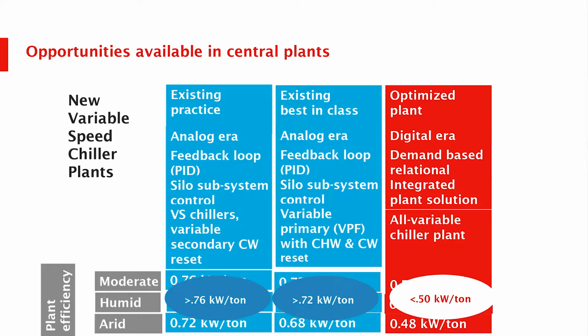I don't want people leaving the room saying the guy from Armstrong said if I do this I'll end up with a plant at 0.5. But we have definitely seen plants that are considerably better. It's a reasonably attainable number for buildings with somewhat moderate climate - not Louisiana, but not Phoenix either - that take advantage of variable flow and sequence equipment so it makes sense to run together.